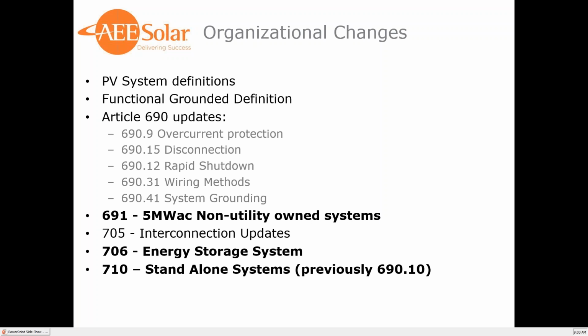There are also a few new articles that were added. 691 is for 5 megawatt AC systems, non-utility owned. We won't go into much detail on this article. It mostly covers fence grounding, access to equipment, and compliance documentation, allowing PEs to review and provide approval if there's no equipment on the market available for what they're looking for. In 705, we have a little bit of updates in the interconnection section, then a new section, 706, for energy storage, and another one, 710, for standalone systems, which is pretty much the old 690.10 section. We're definitely not going to go over everything included in the changes, but we're going to talk about most of what I feel are the important subjects.